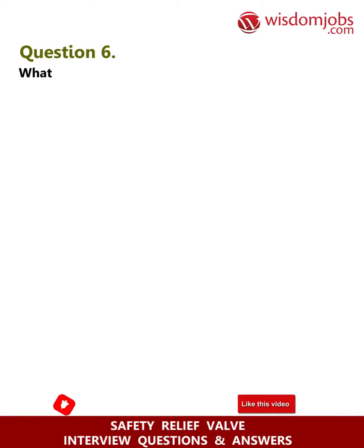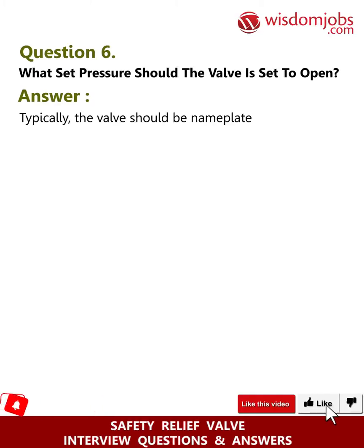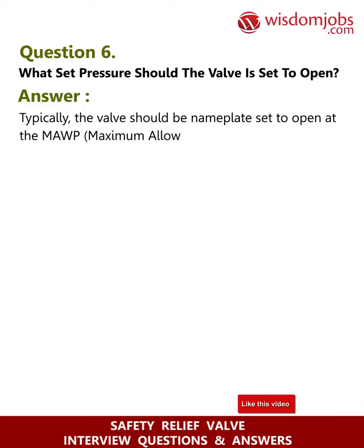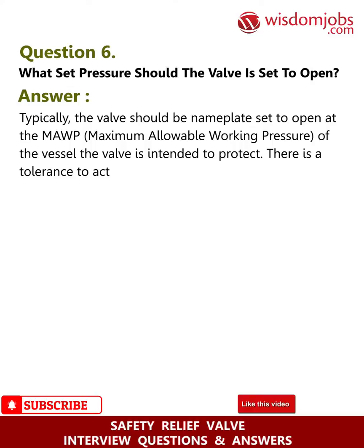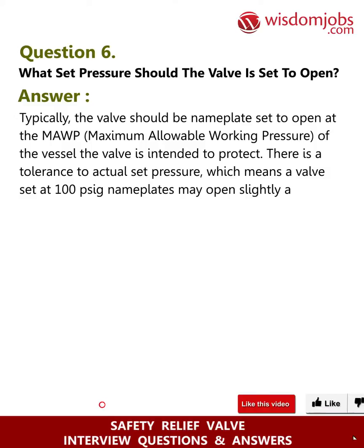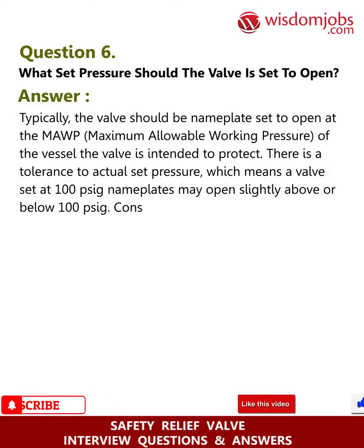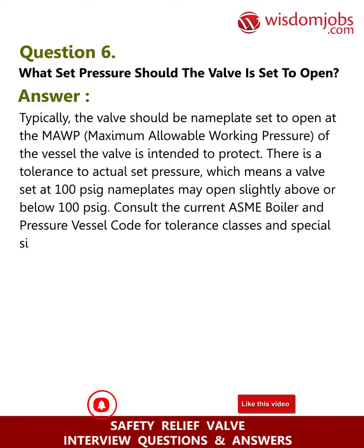Question 6: What set pressure should the valve be set to open? Answer: Typically the valve should be nameplate-set to open at the MAWP (Maximum Allowable Working Pressure) of the vessel the valve is intended to protect. There is a tolerance to actual set pressure, meaning a valve set at 100 PSIG nameplate may open slightly above or below 100 PSIG. Consult the current ASME Boiler and Pressure Vessel Code for tolerance classes and special situations where set pressure may differ from the MAWP.